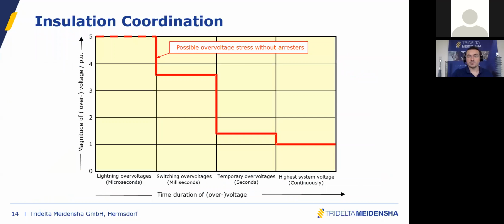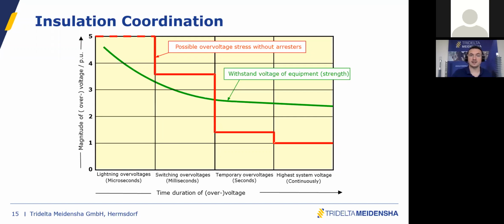Just the diagram, I'm sure that you're familiar with this diagram. The curve in red represents the different stresses that you can see on your system. The important ones are lightning overvoltage, which is of very short duration and very high amplitude, and switching overvoltage, which is in the range of milliseconds and of lower amplitude than lightning. So those two transient overvoltages are quite problematic for the system.